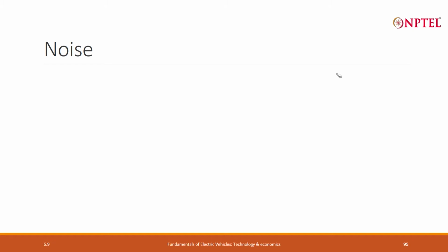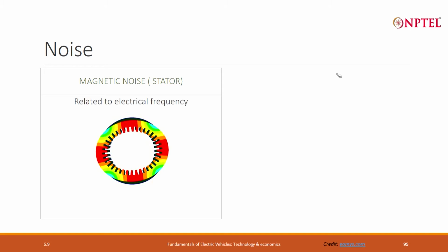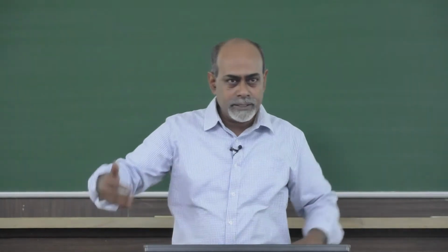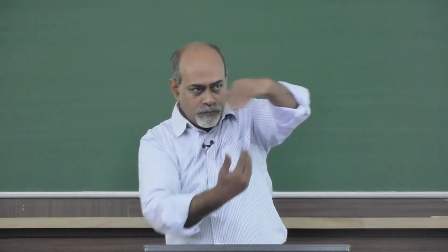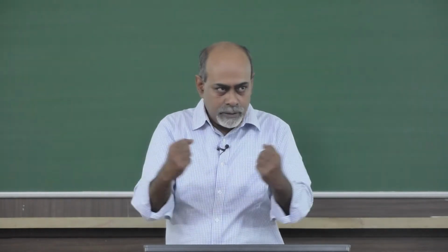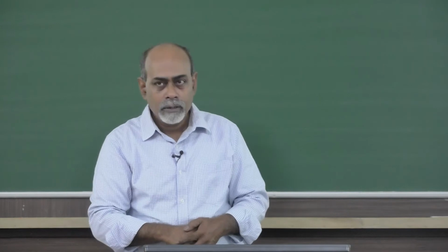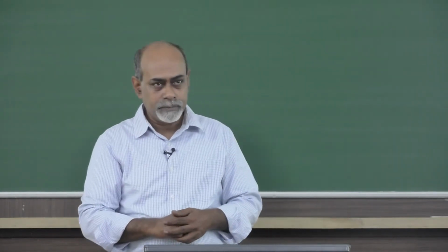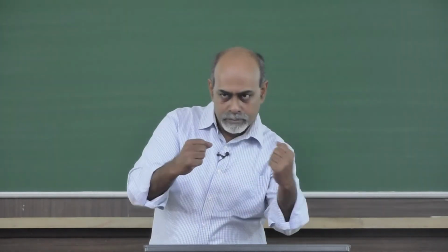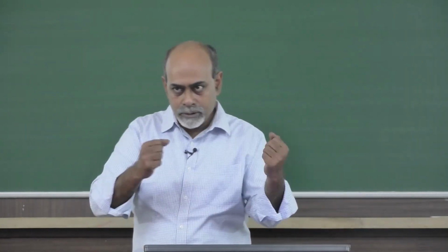The other thing that is a common problem which anybody will complain to you about after you make a motor is the noise. We do not like an engine which is noisy, we do not like a motor that is noisy, and to understand what is noise, we have to see what is the source of it. Noise can come from the stator, and that is called magnetic noise. The rotating magnetomotive force, because of the AC currents that are circulating, causes a wavy circulation of the magnetic field, and that magnetic field will distort the structure of the stator, and at a rapid rate it is getting distorted here, distorted there, in all directions, and that will cause a certain noise.